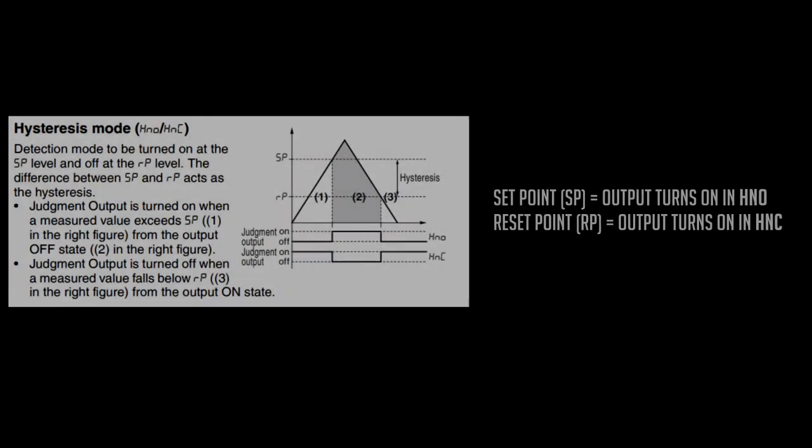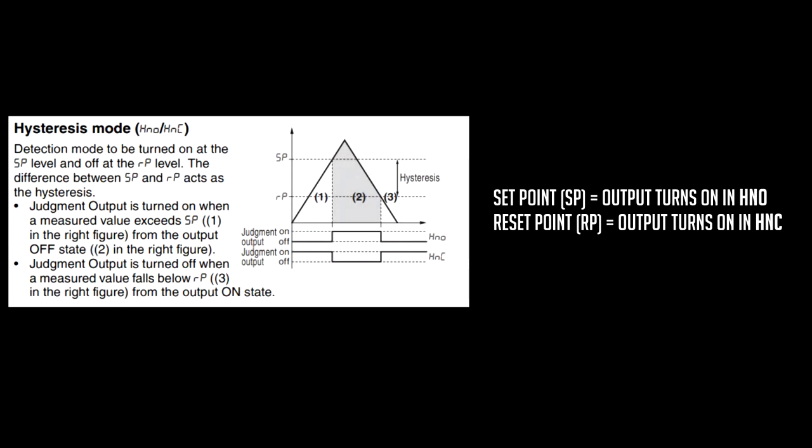So, one of the methods for a discrete output is called hysteresis mode. In hysteresis mode, you have an SP, or a set point, and an RP, or a reset point. For hysteresis normally open, or HNO, your output will turn on at the SP level, or set point. For hysteresis normally closed, or HNC, your output will turn on at the reset point, or RP.